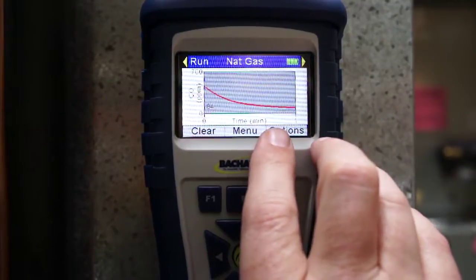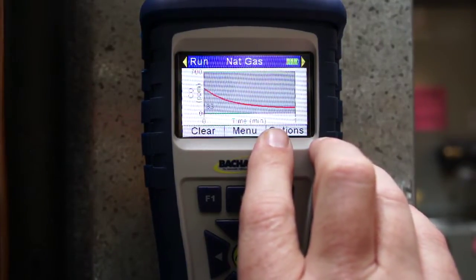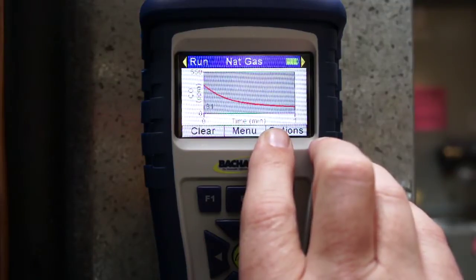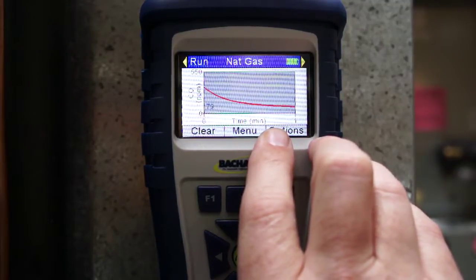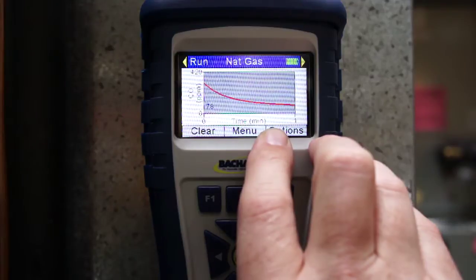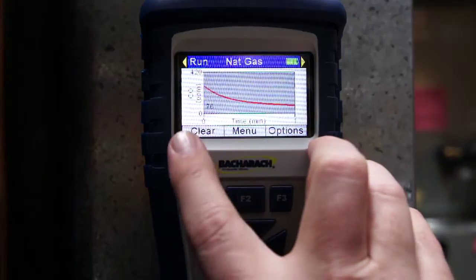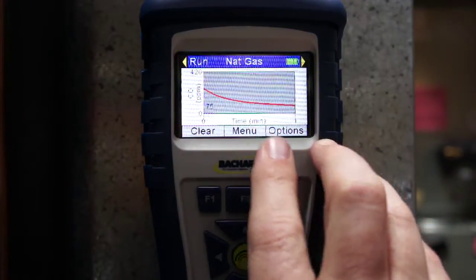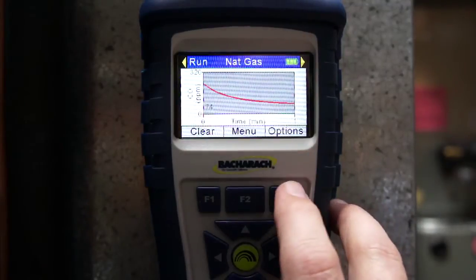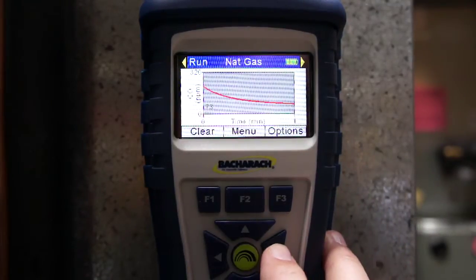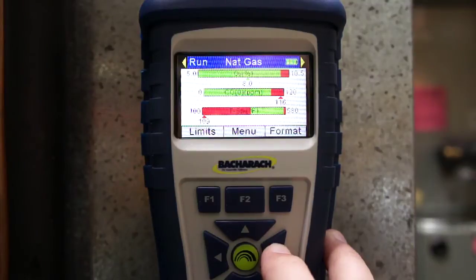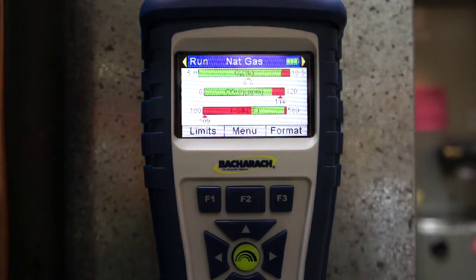For a lot of you guys out there, you're probably going to want to trend your CO reading, so you can look at things like a rough light off, or maybe a shutdown on an oil furnace that's maybe dripping after the burner shuts off. But it allows you to trend that out and see just about anything you want to trend on that. We can also hit the right arrow again, and now I get into my dynamic display here where I've really got a go, no-go bar graph.